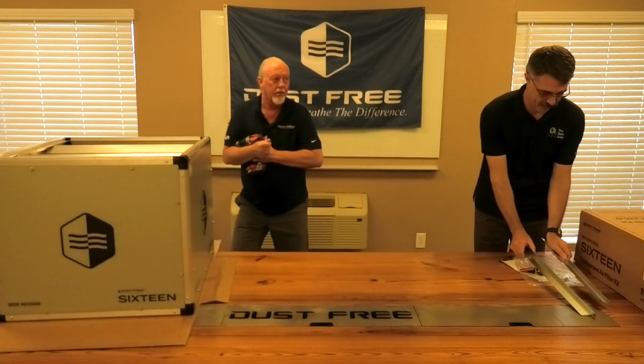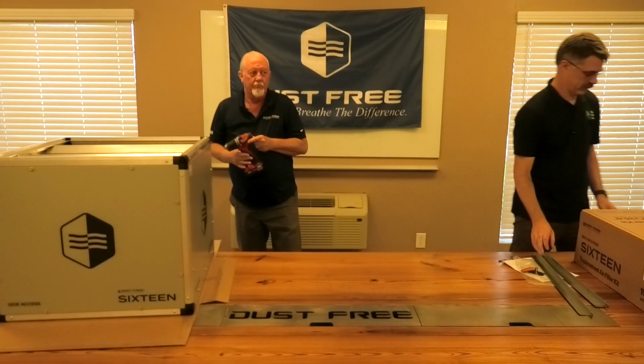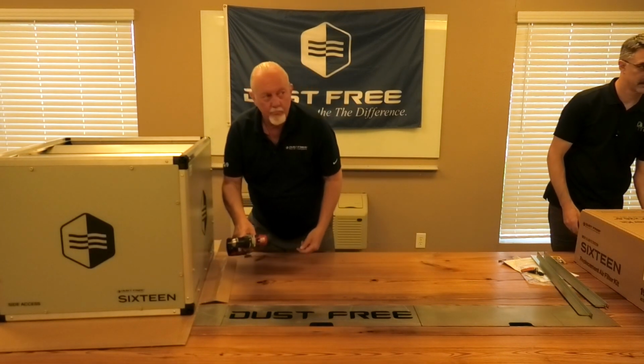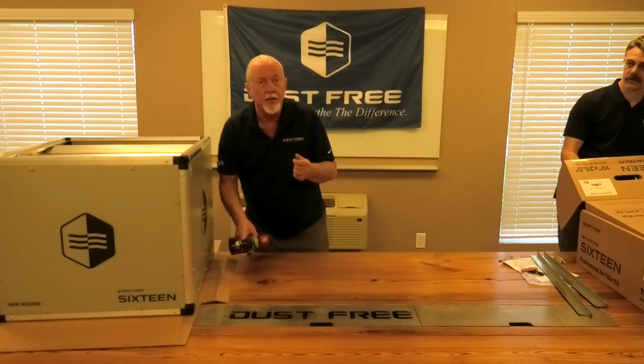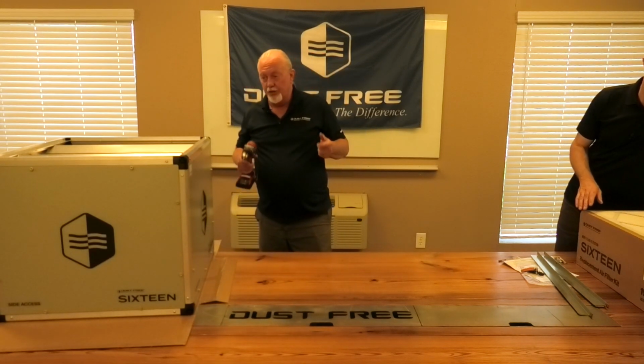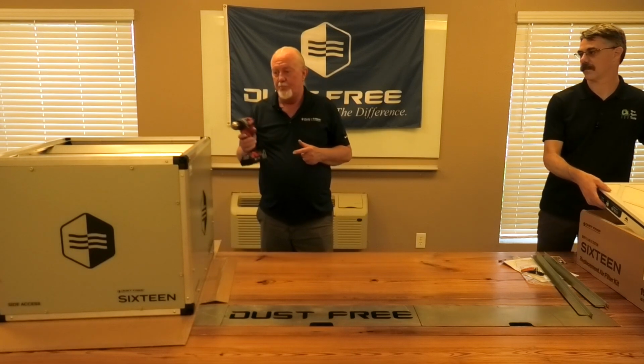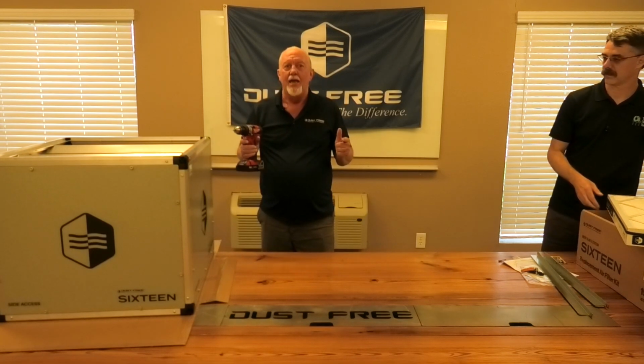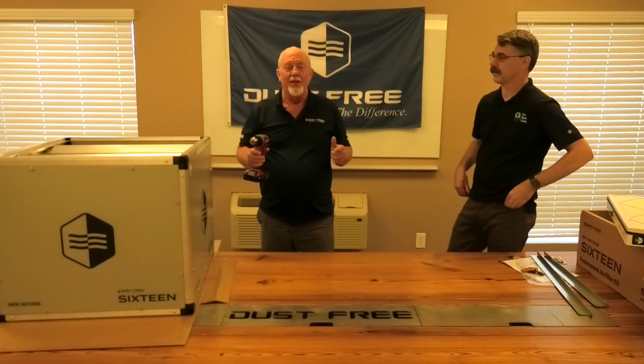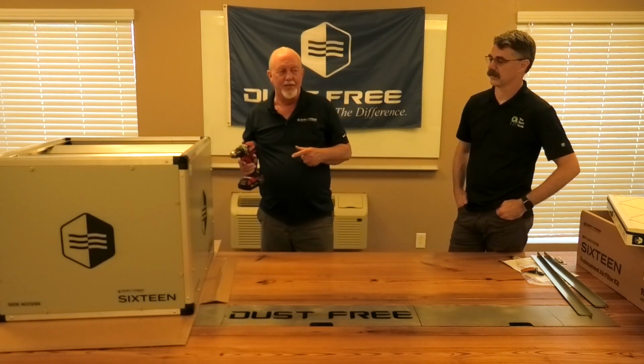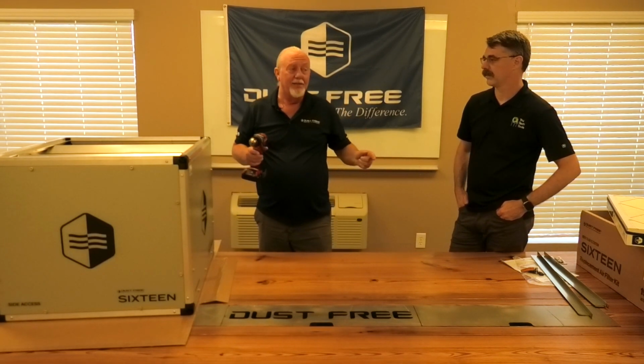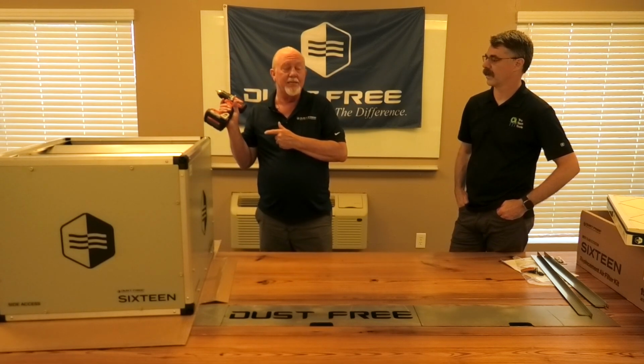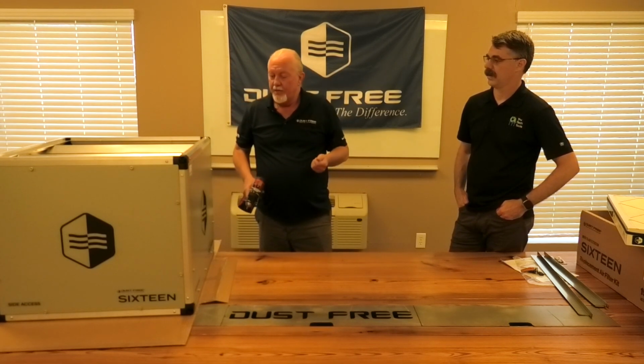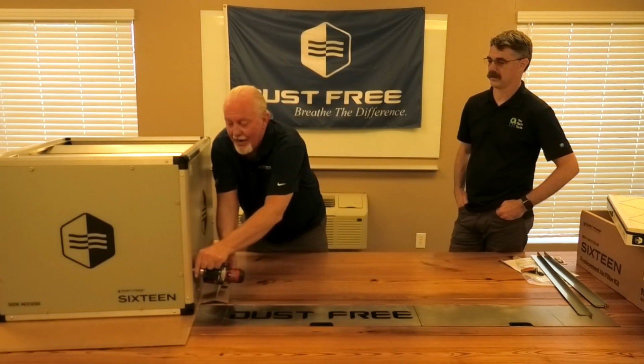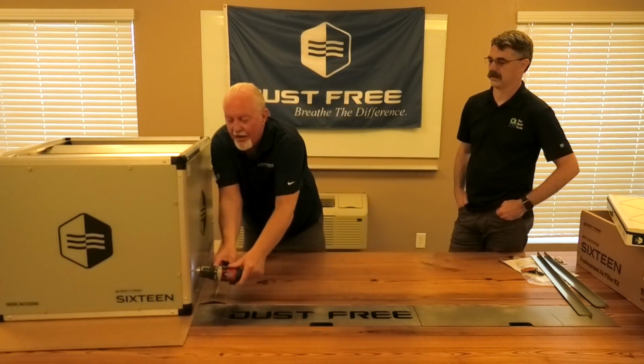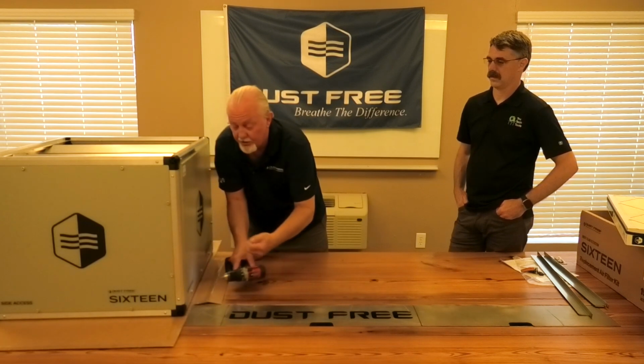One thing generally to keep in mind is if you're going to install this into a system, you'd want to wait as long as you can to put filters in. He brought up a great point. During installation, you want to put this thing together, install it, and when you're ready to do a startup, the last thing you do is put those filters in. Keep them in the box, keep the box closed, keep it out of the attic or crawl space until you're ready to put them in. Because the final result is having clean air, and if you dirty up the filters, that's kind of counterproductive. Thank you for that good tip.